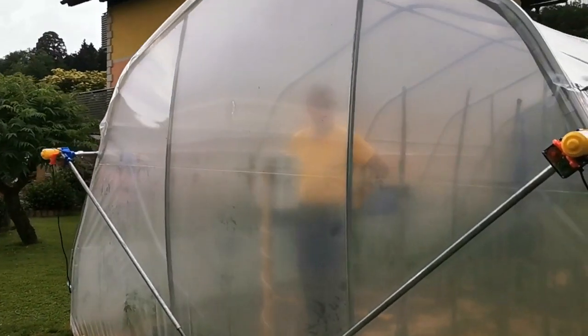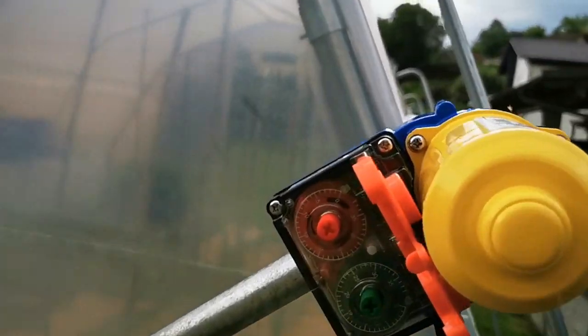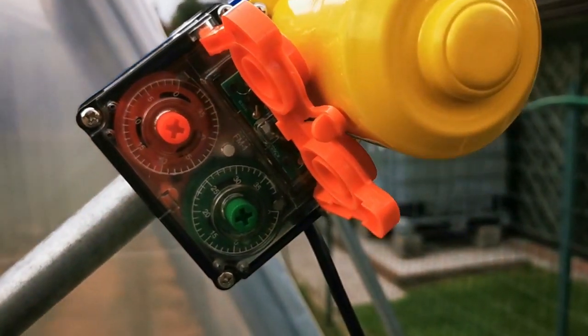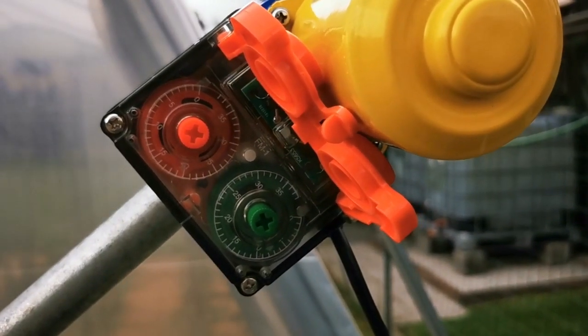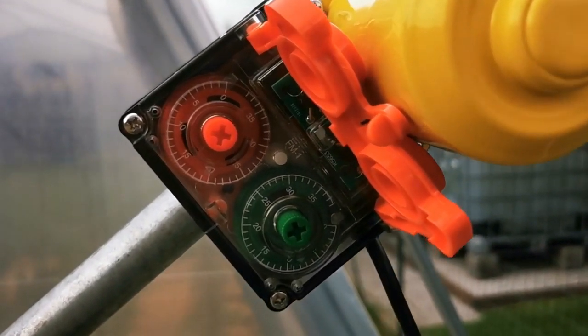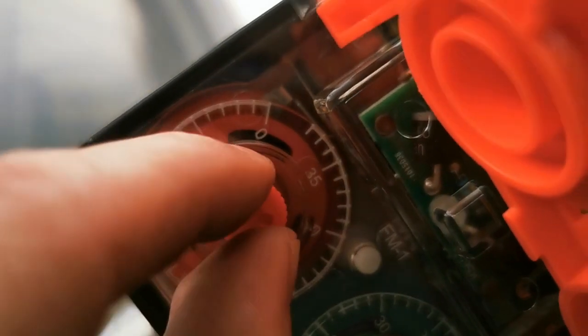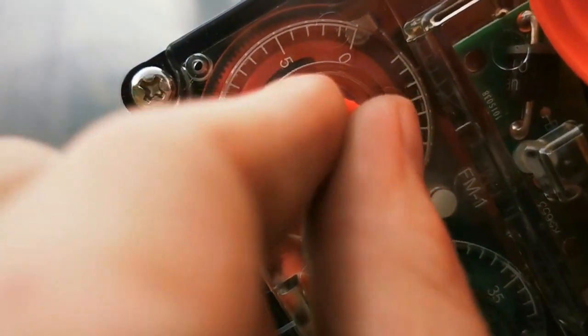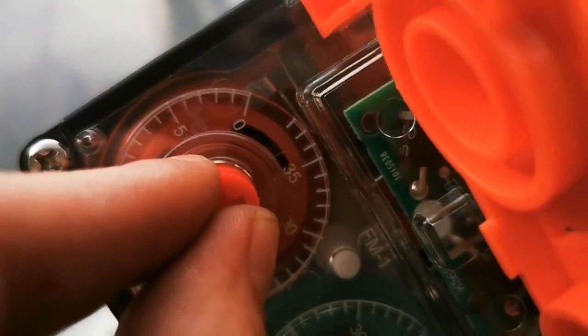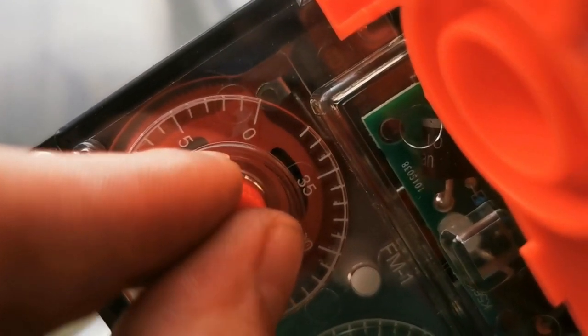Same as before, hold the up button for 1 second to see the color of the end switch to be set. In this case it is red. Set the arrow as close as possible to the limit switch contact. We do the same on the other side.